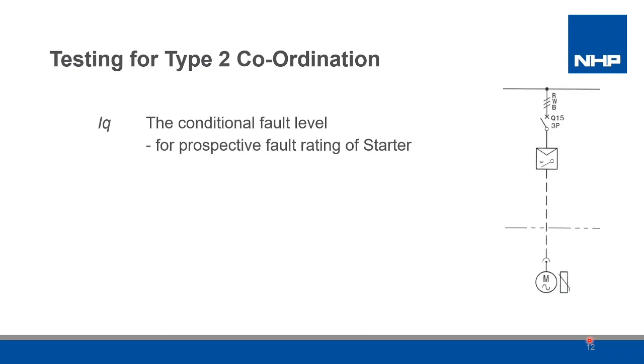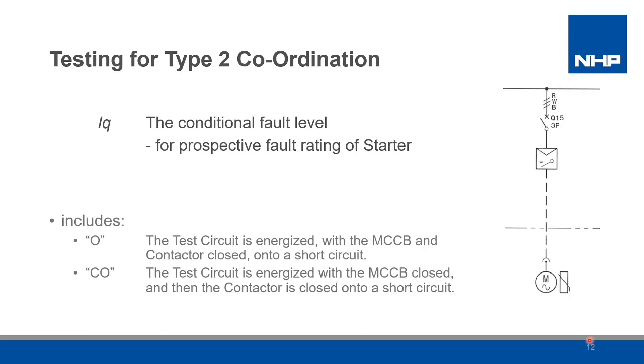IQ is the test level for which the starter combination is tested to, being the nominated prospective fault for the table. The two short circuit tests are performed in sequence. As with the R sequence, for the O test, the MCCB opens to protect the circuit, and in the CO test, the contactor closes, then the MCCB opens to protect the circuit.